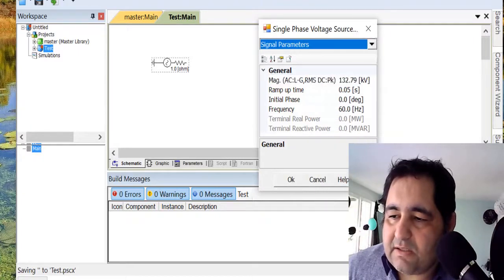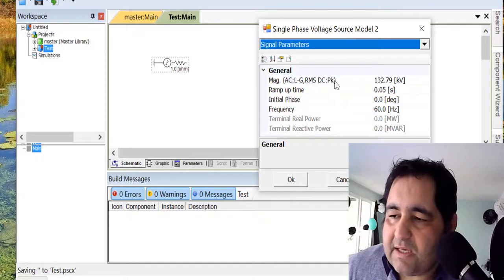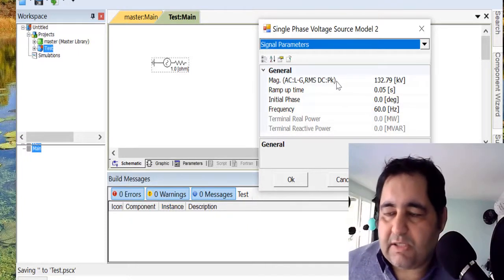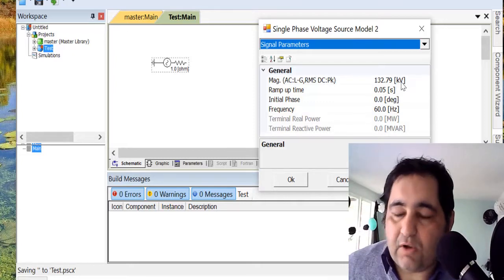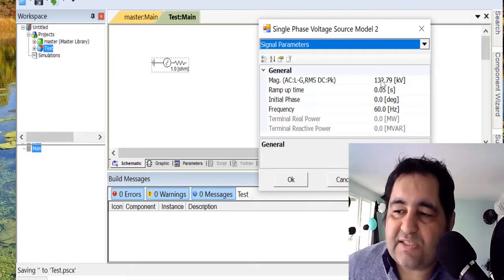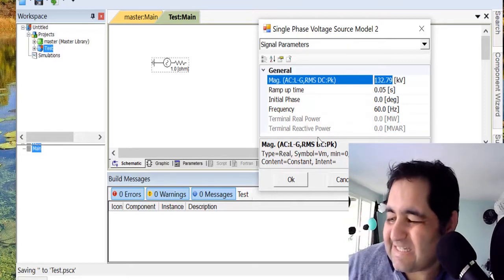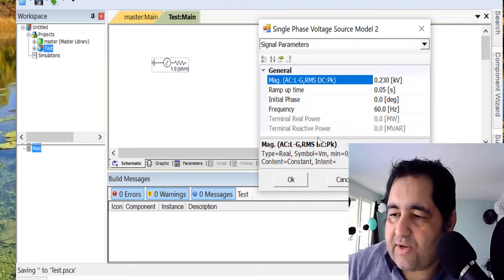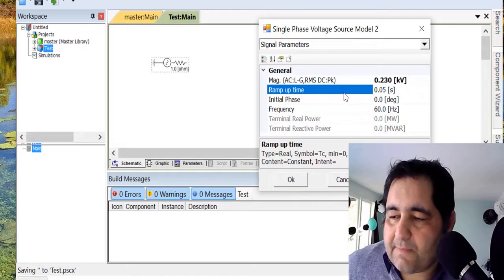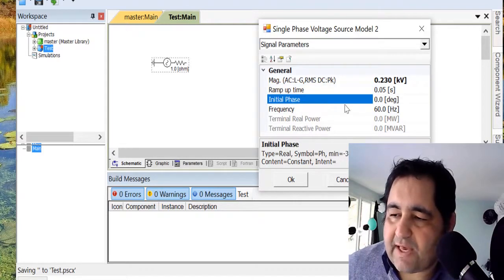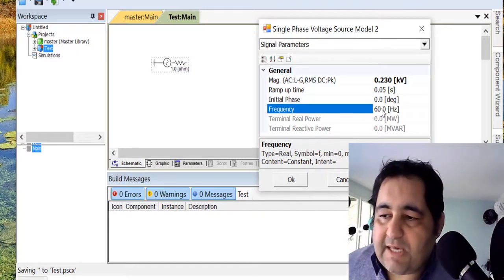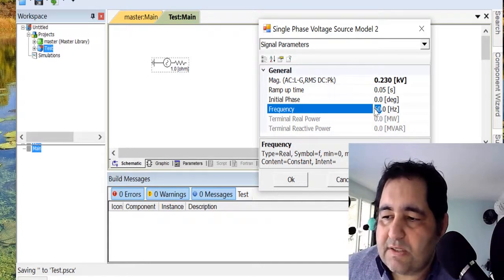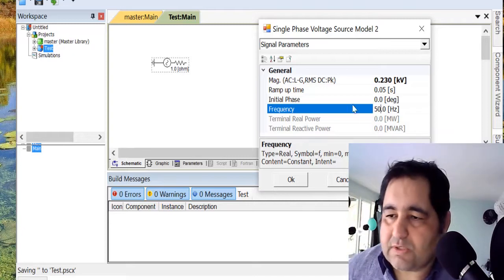After the configuration, we have other stuff to take care of. One is signal parameters, where you can decide the parameters. You can see the magnitude: AC, RMS, DC peak. The voltage is in kilovolts. If I want 230 volts, I need to write 0.230 like that. Ramp-up time 0.05, initial phase zero. The frequency—this software is American-made, so by default it's 60 hertz. We can change it to 50 hertz or any other frequency you want.